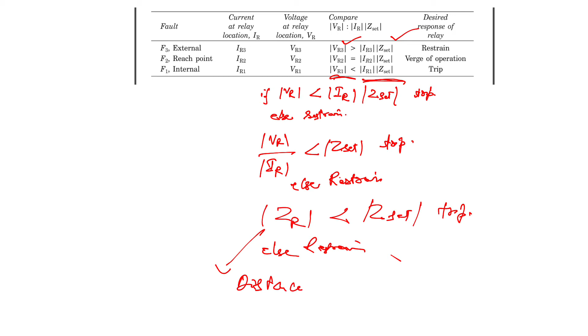Now because of the simple series model of the faulted line, the line impedance is directly proportional to the distance, and so the name distance relay. So we can call it the distance relay. And such a relay is also known as the under impedance relay, because V by I is actually the impedance.